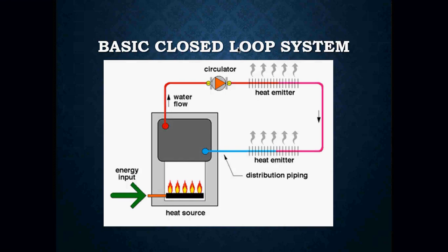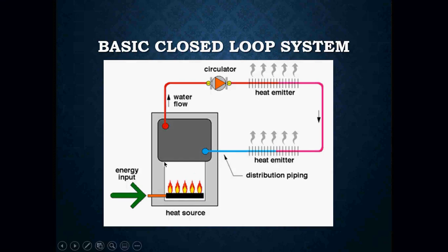Here's an example of a basic closed-loop system. We've got our heat source with energy input — this could be gas, oil, propane, or even electrical. Something that's going to heat up the water. Our boiler is filled with water. Here's our distribution piping — water comes out of the top through our circulator, which flows water through our circuit and through our heat emitters, and then makes its way right back to the boiler. That circle continues until the thermostat tells the boiler and everything else to shut off.